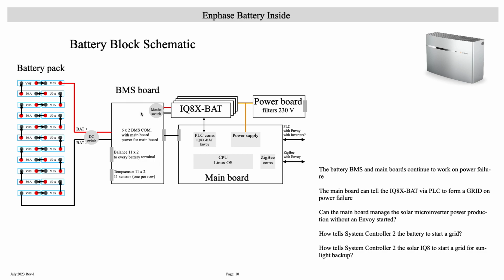The battery switch has a MOSFET and power measuring stuff inside, and then it passes the voltage to the inverter, which powers the house or home, or goes the other way around to push energy back into the battery. So think of it as almost connected either going in or going back. This is just some maintenance stuff for balancing, and this balancing is the same story for every battery vendor — they need to balance the batteries, because if one battery has a different voltage compared to the others, this will limit the energy, or if the voltage is very low, it won't permit the whole battery to work, because everything is in series.